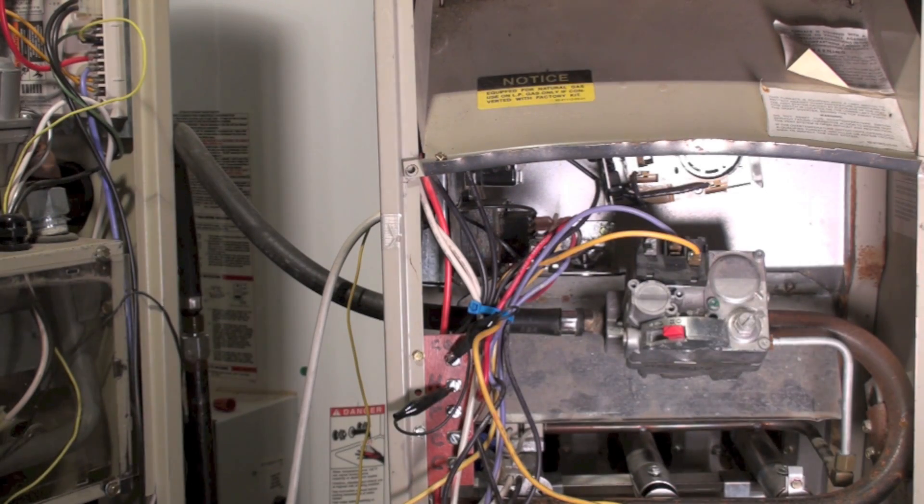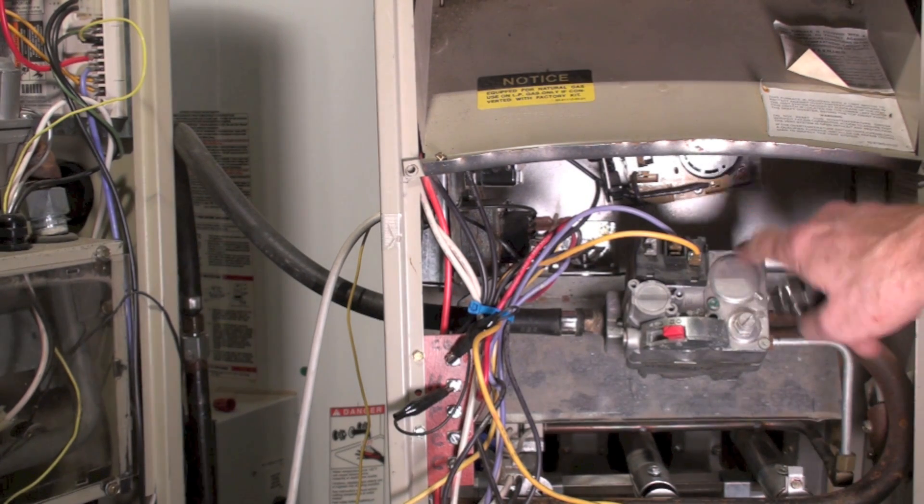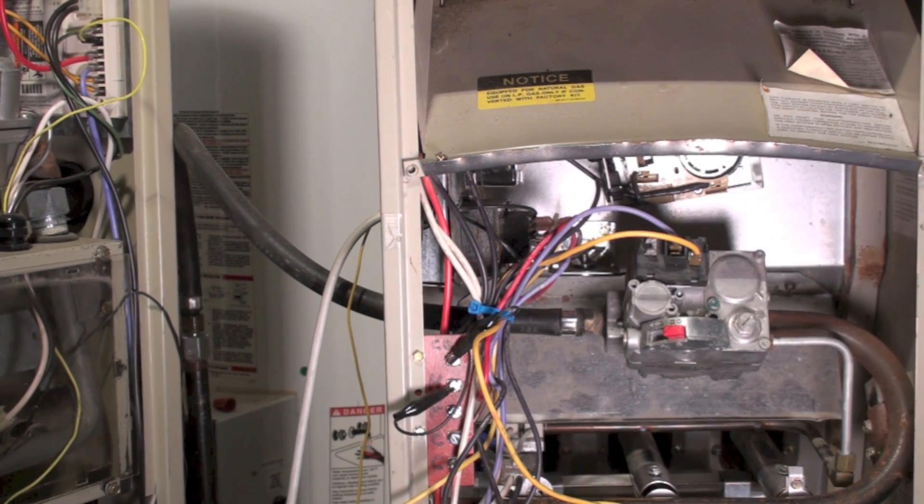You can see you got it going there. As you have seen, it has rolled out quite a bit there, probably enough to possibly damage this valve. It did get pretty hot, but it finally did kick off this manual reset rollout switch.